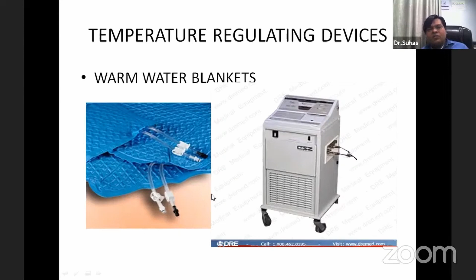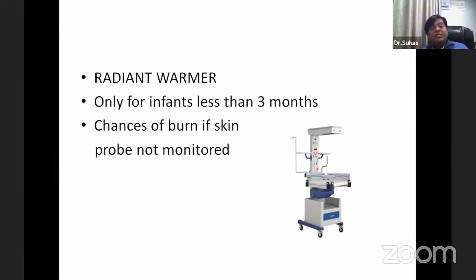So this is ideal. Another thing, if the infant is less than 3 months, we can use a radiant warmer, but in a radiant warmer, the child needs constant monitoring. The skin probe is attached, which will convey the skin temperature to the machine, and according to that, the percentage of heat of the radiant warmer will be decided. But if the skin probe is detached, a falsely low temperature will be detected by the machine and it will heat more. So there are chances of burns. So the skin probe should be stringently monitored. Another disadvantage is that it is only useful for children less than 3 months because the trolley is of very small size. So another is the warm air mattress.